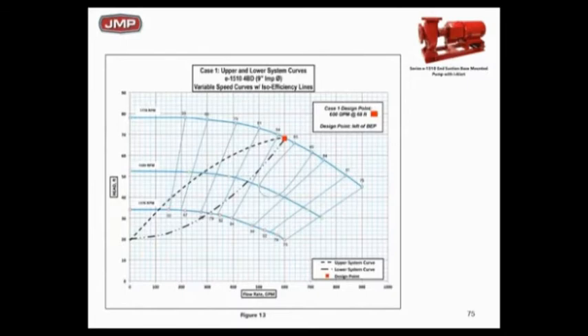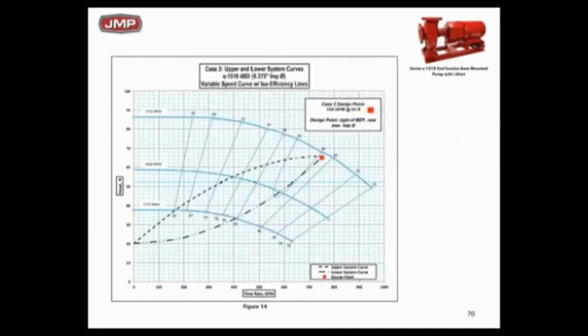But I'm living dangerously and you best be sure you've got the right pump head. You best be sure you've got the right pump head. And that's the issue. You've got to make that decision. We would not argue with you at all that it might be slightly higher if you do a good pump head loss calculation. If you don't, you may fall off the pump curve. You don't have much safety. You're losing your safety package.